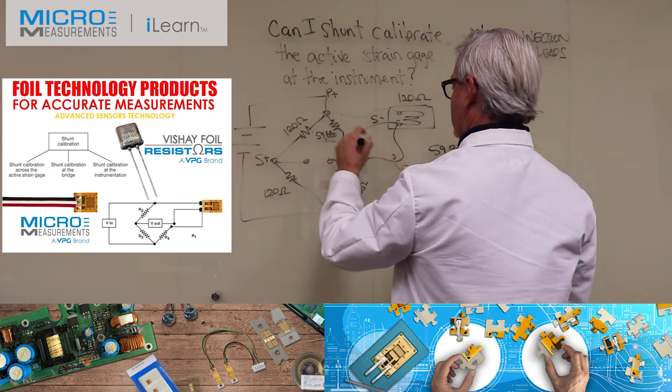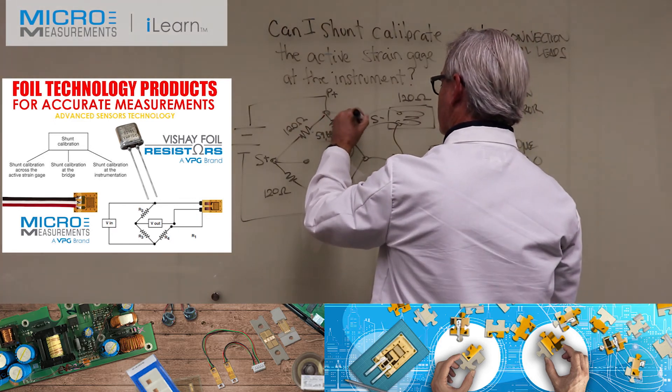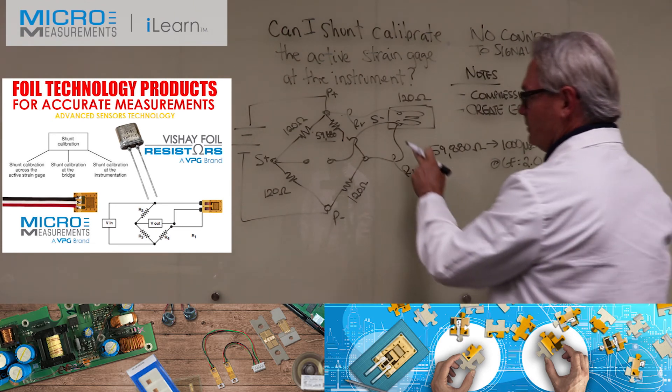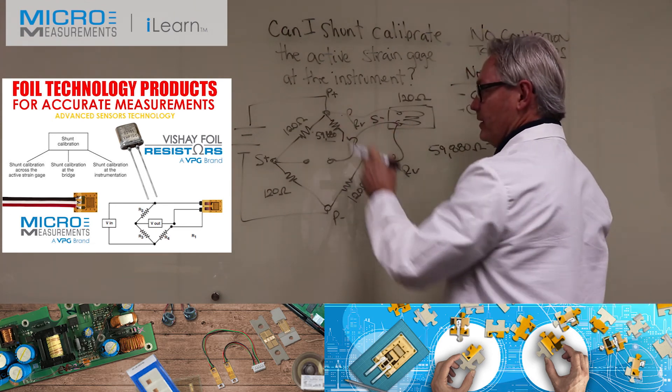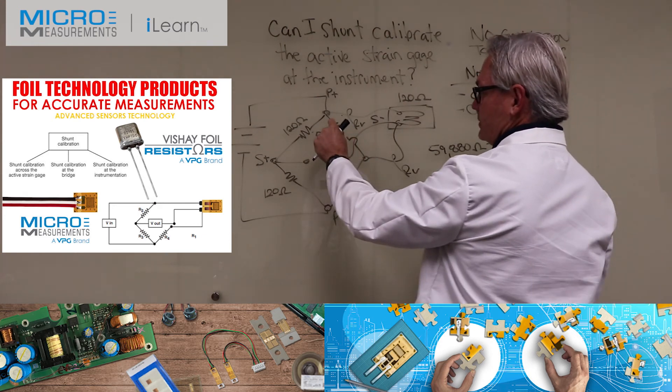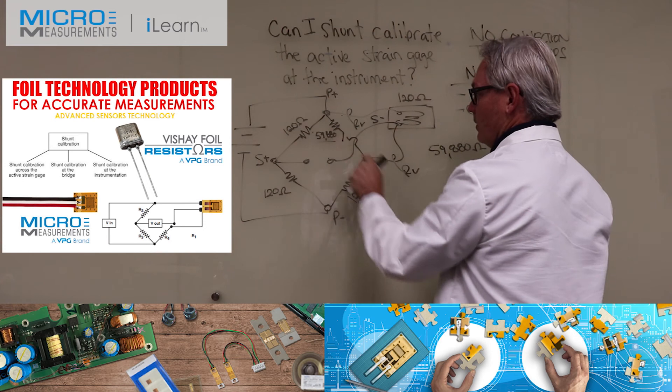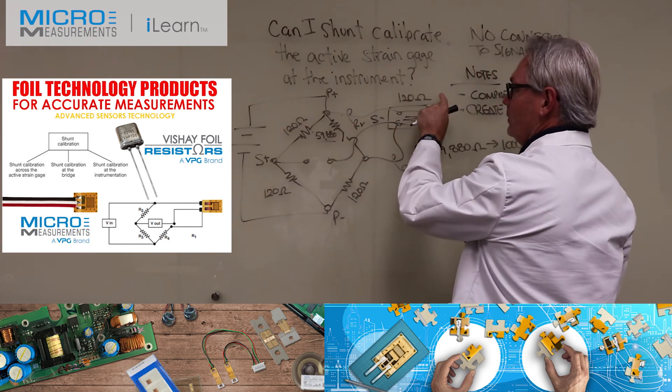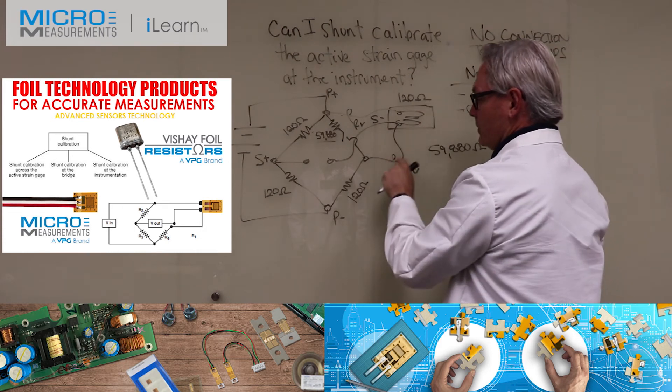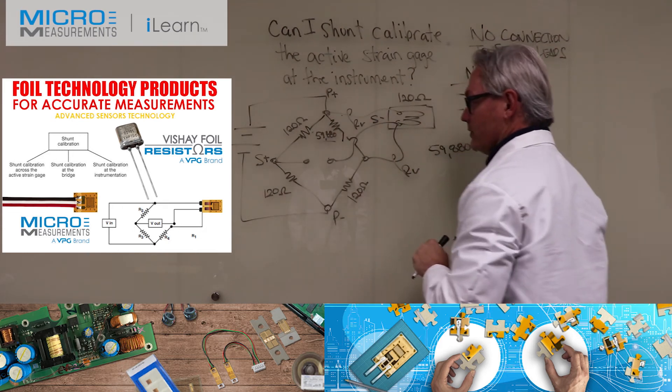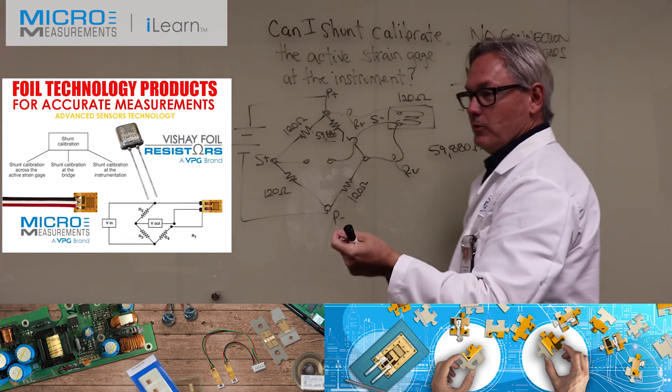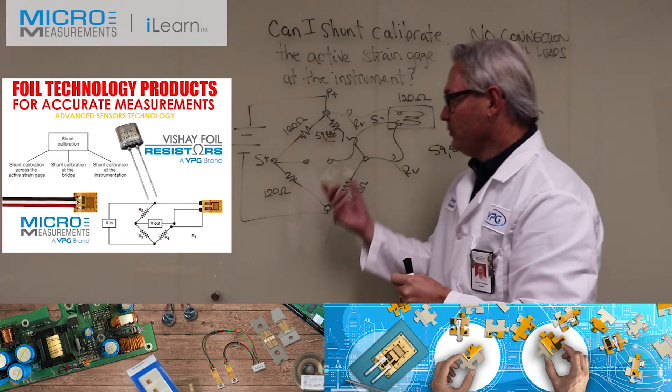The problem is the resistance of these wires. Why is that a problem? Well, the resistance of the wires can vary depending on the length of the wires. And when you take this resistor and you shunt calibrate across these two points, you're not pulling in just the resistance of the gauge that you're shunting, but you're also shunting the resistance of these wires.